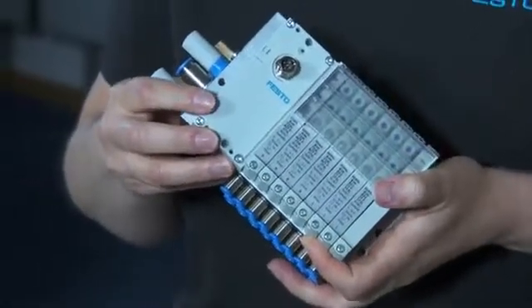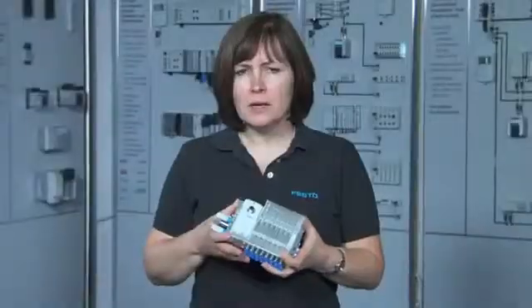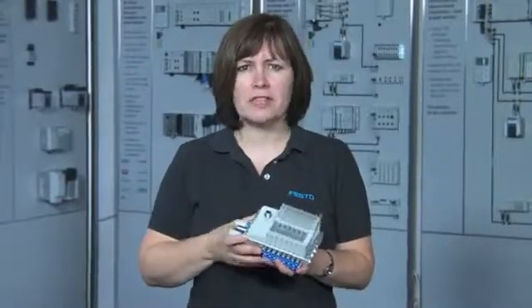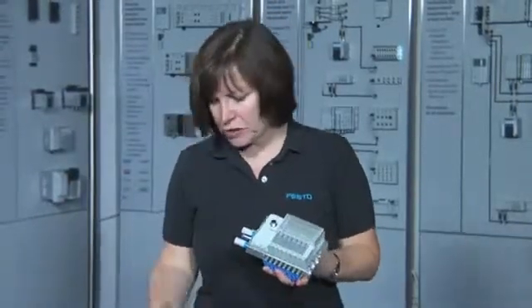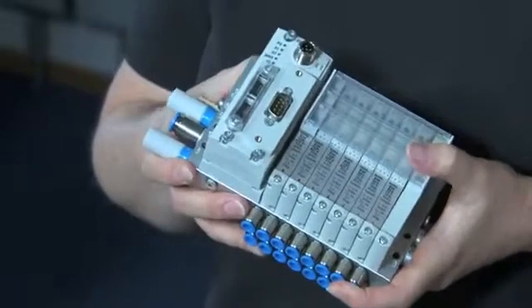And then of course we have communication networks. With our innovative connection method using IO-Link, an industry standard point-to-point network, we can connect directly to any IO-Link master. But if you would prefer a field bus or industrial Ethernet network, just put the correct module on top of the IO-Link port, like this, and it becomes a field bus or Ethernet valve terminal.